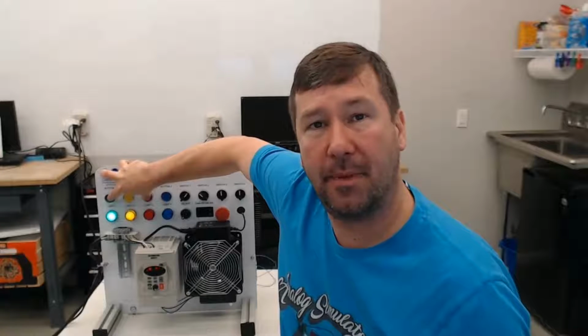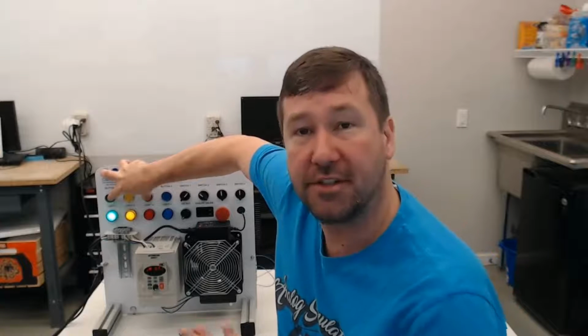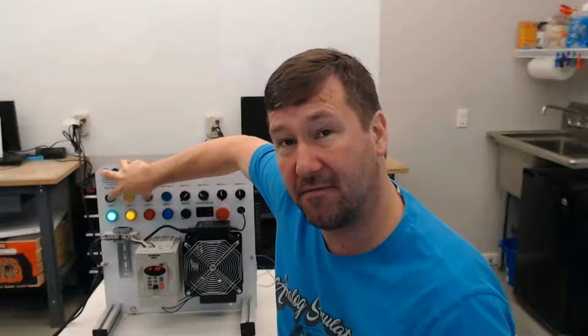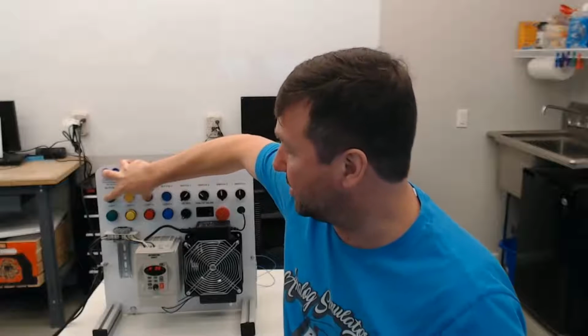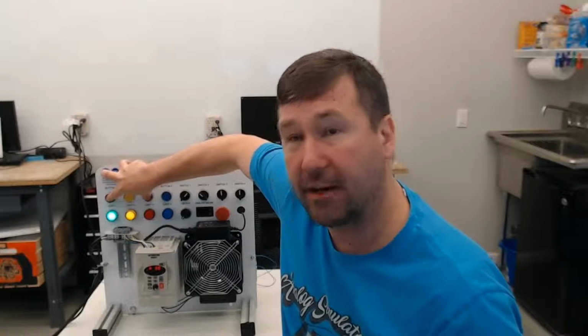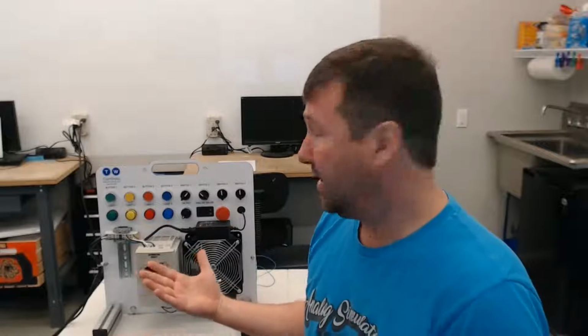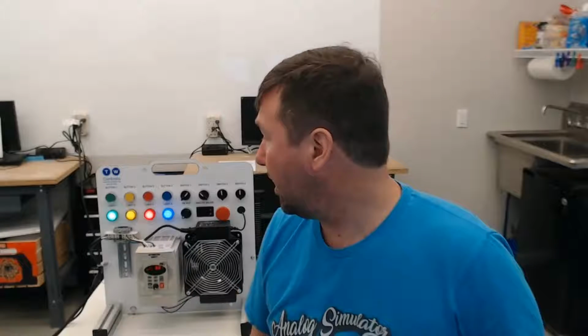Now, that could be a danger depending on your situation, but also this is a very important maintenance feature. It lets them bump the motor very easily. And let me tell you, if you don't give a maintenance person a way to bump a motor, then they're going to be jabbing a screwdriver into the terminals, which can be a lot more dangerous situation than the stop button.